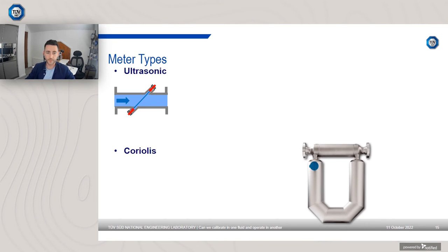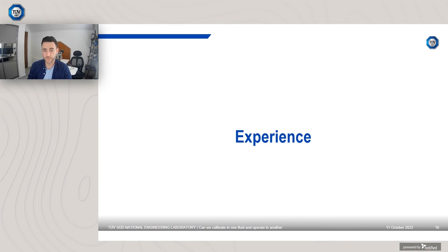However, the other newer technology, an extremely popular meter, at least 90% of the meters we calibrate in the air now, is the Coriolis meter. It comes in one device that is suitable for both gas and liquid use. So a Coriolis meter potentially could be calibrated in water and then used in gas. That's the type of device we'd also be interested in exploring with respect to LNG or liquid CO2. Could you calibrate it in water and use it in gas CO2? Could you use it with liquid CO2? Could you use it with LNG and other challenging fluid properties? Well, some of the experiences I want to share with you are from some of our research here at NEL.